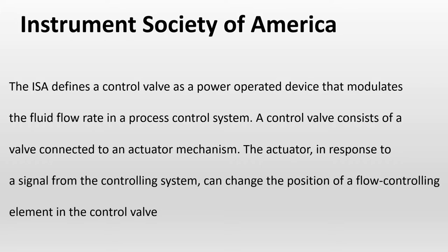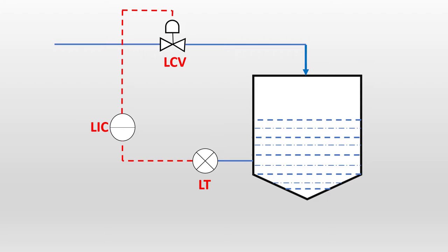Now let's see how a control valve controls the process fluid. There is a vessel or tank with process fluid inside. A level transmitter continuously measures the level and sends a signal to the LIC — the Level Indication Controller. The controller has a set point, a manipulated variable, and a process variable. It performs calculations and an algorithm, then sends a signal to the level control valve.